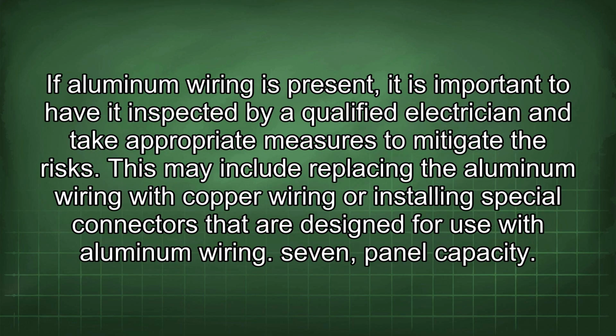If aluminum wiring is present, it is important to have it inspected by a qualified electrician and take appropriate measures to mitigate the risks. This may include replacing the aluminum wiring with copper wiring or installing special connectors that are designed for use with aluminum wiring.